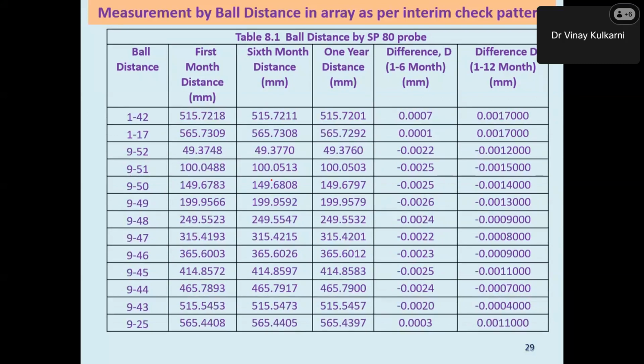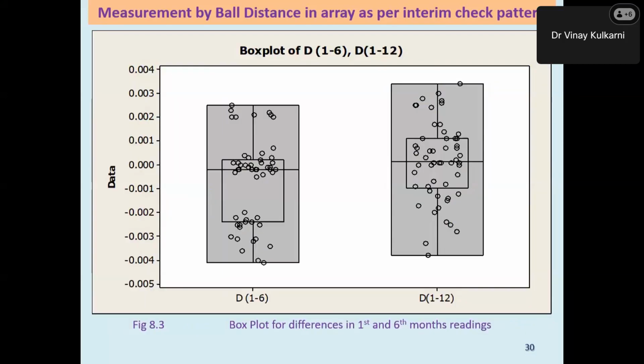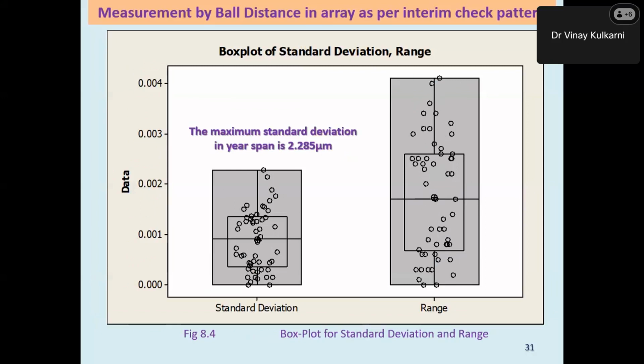Okay, when we make it in a horizontal position, this is a box plot, dear friends. Here, as you can see in this box plot, the measurement here is minus 0.004 to 0.0025, and 1 to 12 is in fact slightly increased, but it is very much less than the yaw error of the CMM machine. That's why we can say that this is very stable. The maximum standard deviation in the year span is 2.285 micrometers.